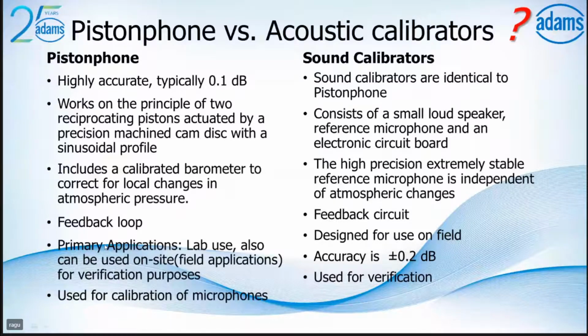It can also be used for a single frequency level check. So in any field application, pistonphones can still be used. It is not that you need not buy a pistonphone. It is just much more accurate than a sound calibrator. So the sound calibrators are used to verify the microphone or to ensure the working functionality of the microphone that you're going to use for the measurement. The accuracy is 0.2 dB.